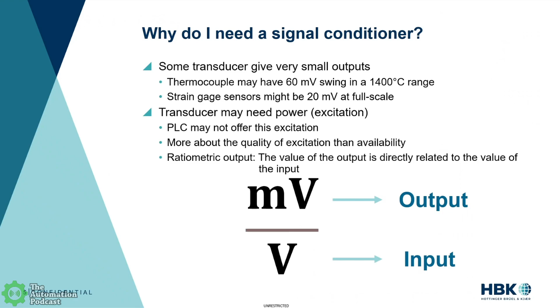No, I don't want to steal your thunder here, but I wanted to throw out some others too. So transducers, we totally get it, especially with what HBK does. But there's other places too. It could be that you need to run an analog signal much longer than you would normally want to, or you may have to interface with an existing piece of equipment. Typically when you build new, everything's going to be 4 to 20, everybody's happy. But what if you have to interface with an existing piece of equipment? It can be, in many cases, a lot less expensive to get a signal conditioner for that one channel than to buy a whole other analog card for your PLC that supports that range. So lots of different places where you might need a signal conditioner.